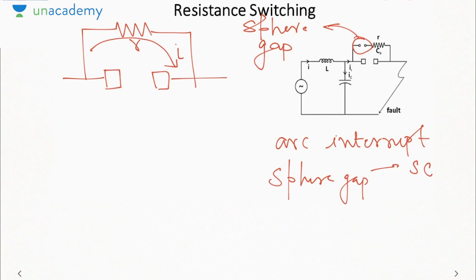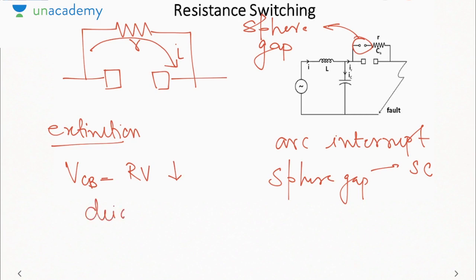But after the arc extinction, the only voltage that appears across the circuit breaker is the recovery voltage, which is lesser in magnitude. If it is lesser in magnitude, then the sphere gap will deionize and it will open circuit the resistance. Okay, after extinction, VCB is equal to RV, which is less, due to which deionization takes place and the sphere gap becomes open circuited. So that is how we use the sphere gap in series with the resistance to connect or disconnect the resistance.